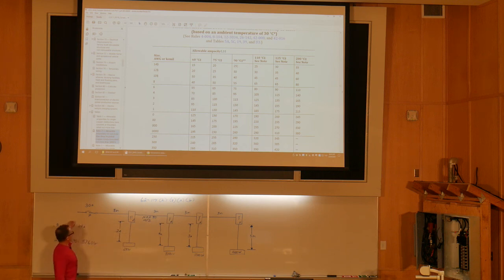we use NMD 90, 10-2 all the way through here, and then we're just going to drop off from the thermostats and pick up the heaters. Number 14. And number 14. Now, there possibly could be a chance that somewhere in here you could have reduced the size of the conductor as well. But what we're just trying to teach you here is how to apply the rule, all right? Because you've got to keep it simple for your students to understand the basics here. As long as the conductor is at least 1/3 of the overcurrent device and is not longer than 7.5 meters, we can reduce the size of it.